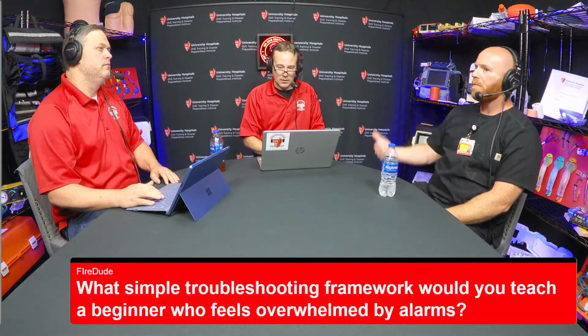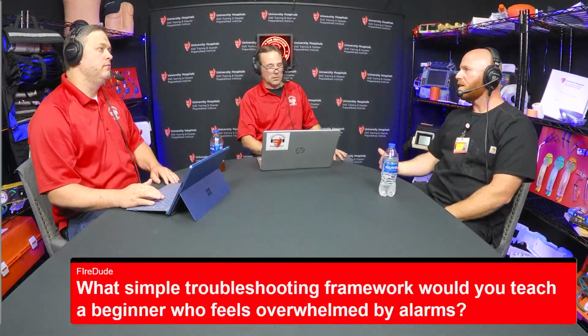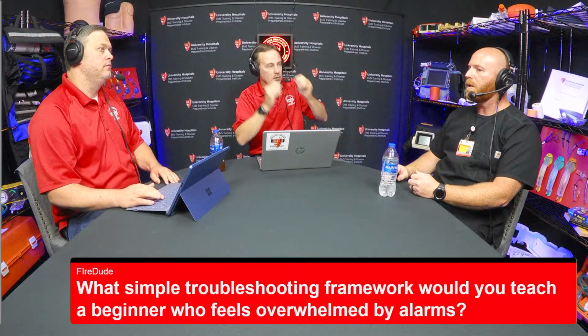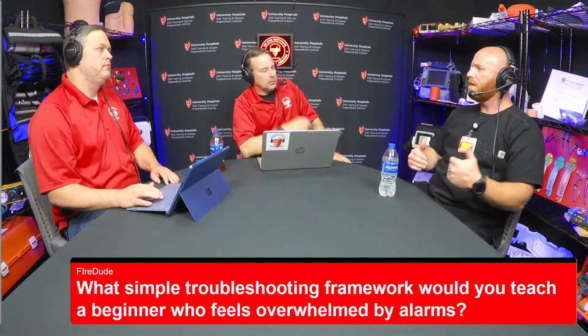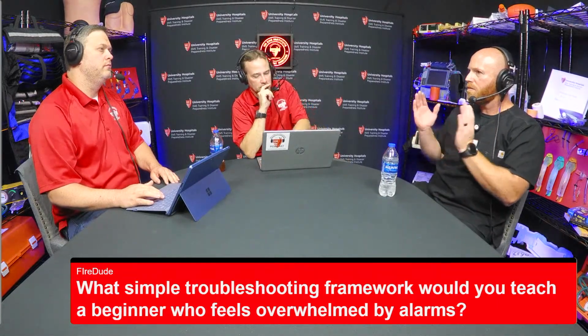So if it's a high pressure alarm, there's all sorts of different things that can cause that. But we start looking at anything that the ventilator would experience as it's trying to blow the air in that would cause the pressures to spike. So we think about kinked off tubing. We think about a patient that maybe is biting down on their ET tube, or perhaps they coughed up a big mucus plug into the tube. And then we start thinking about, maybe they're having bronchospasm and their airway pressures are now going up. So we have to look at the alarm and then try and diagnose from there. And then we can continue on and on with that.